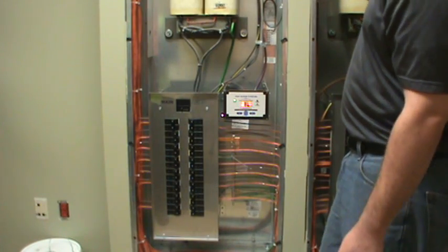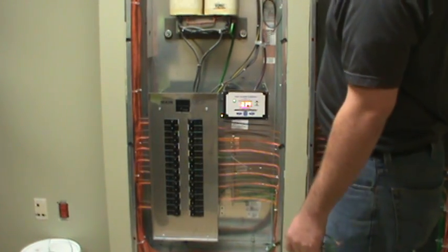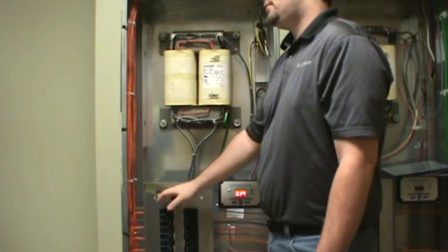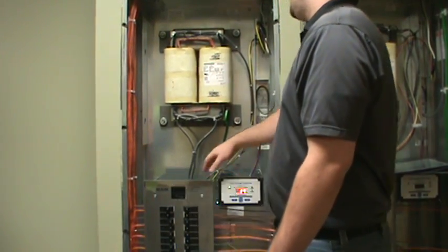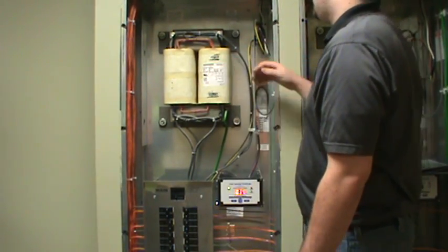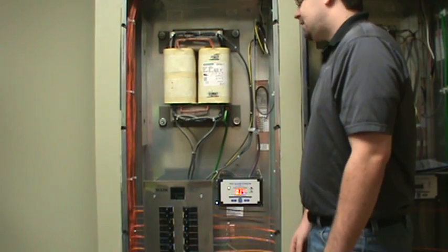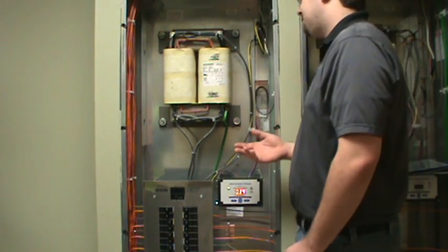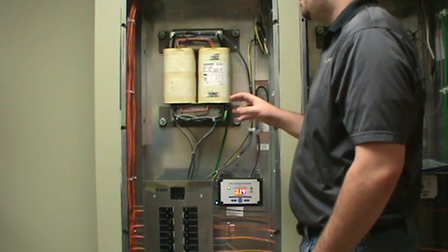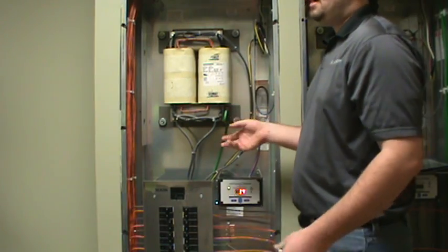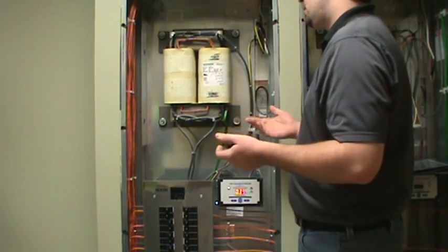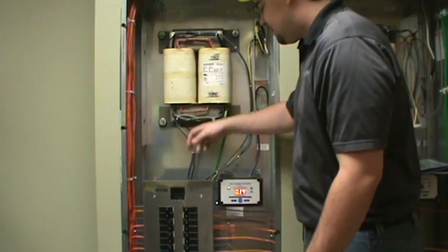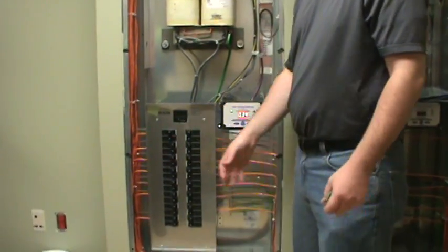Basic physical breakdown of the panel. We have the outside 480 volts coming in through our main breaker, up to the isolated transformer. That steps down the 480 to 120 isolated. We actually have about 60 volts on each line to ground, in phase, added together, 120 phase to phase. From there we go down to our breaker and then out to the receptacles and the boom equipment in the room.